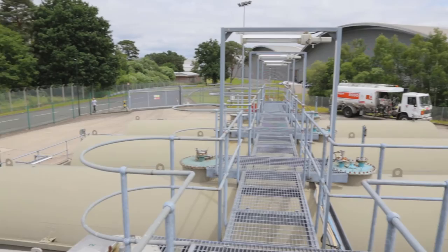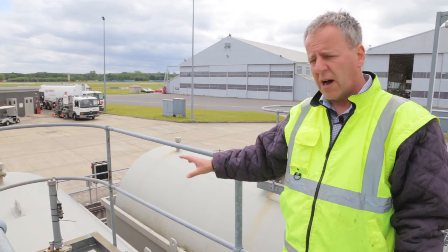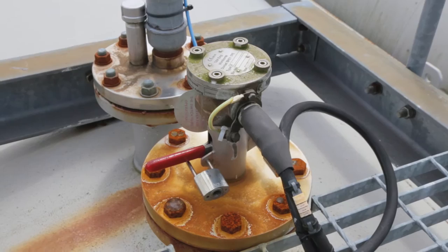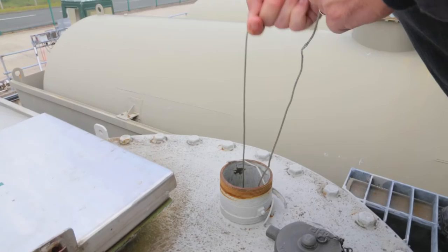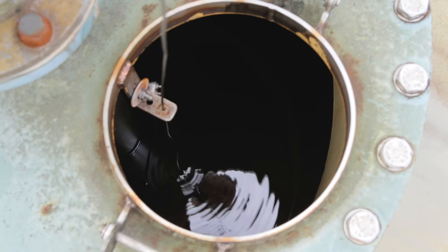There are checks that have to be done on the storage tanks themselves: daily, weekly, quarterly, six-monthly and annual. The daily and weekly checks include inspecting tank vents to make sure there is no debris or birds nesting, keeping vents clean and free. A very important safety item — particularly since the Buncefield incident — is high-level alarms, which must be tested to ensure tanks aren't overfilled. Another important check is the floating suction, which ensures the suction arm delivering fuel to refuelers draws from the mid-section of the fuel, not from the bottom of the tank where debris, dirt and sediment may be collecting.